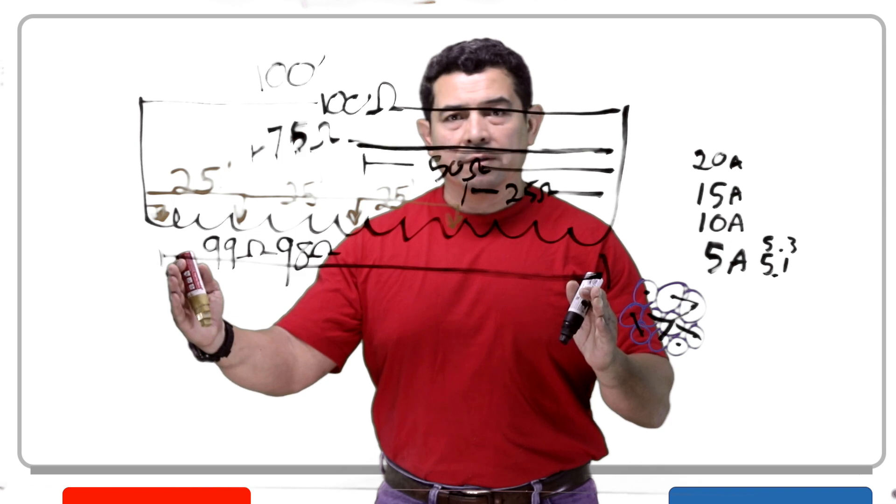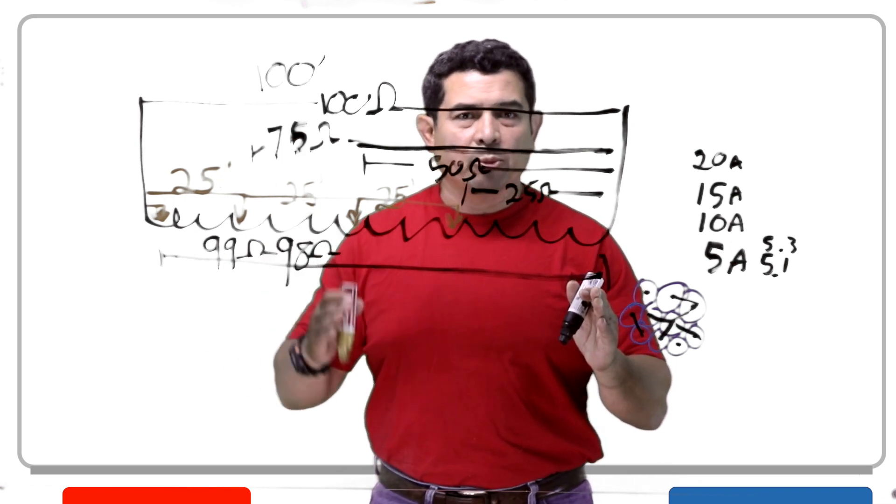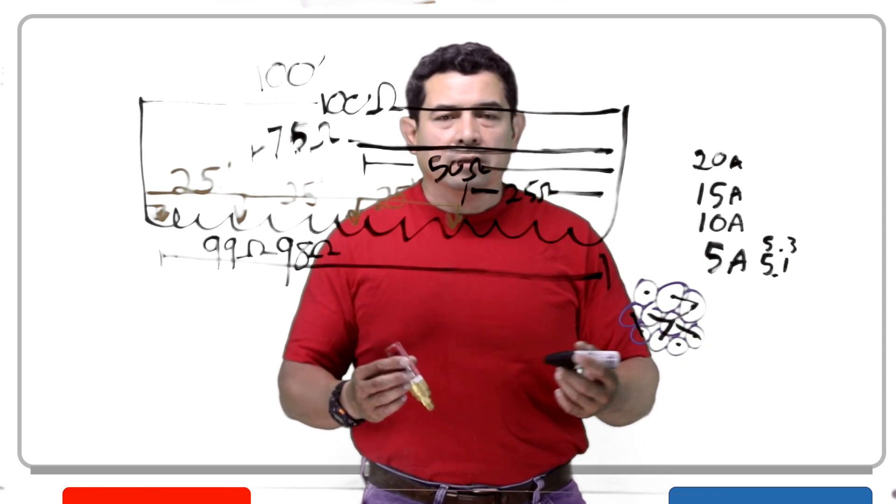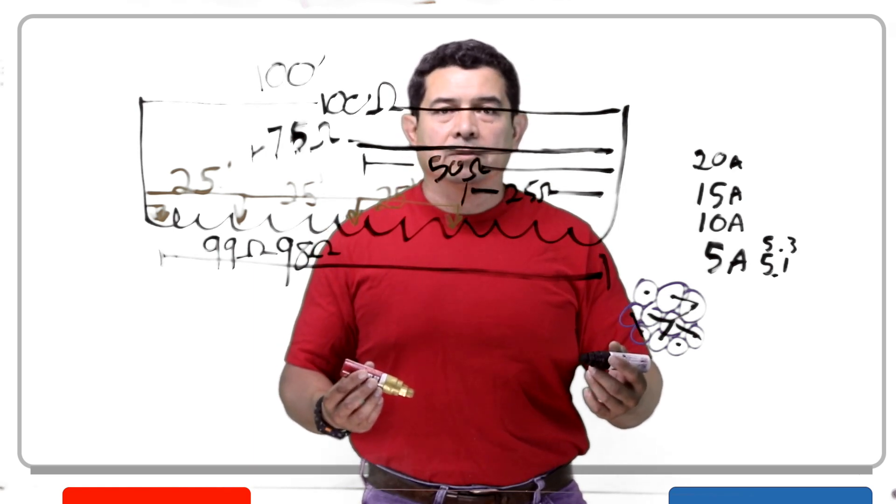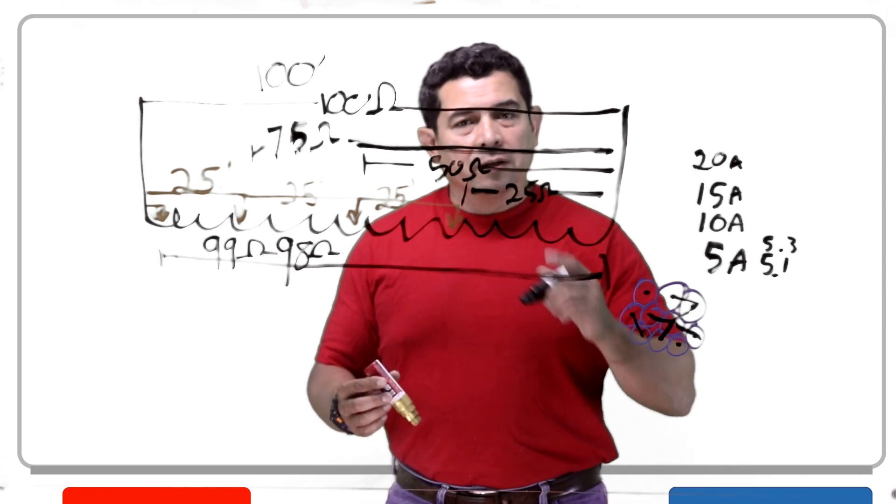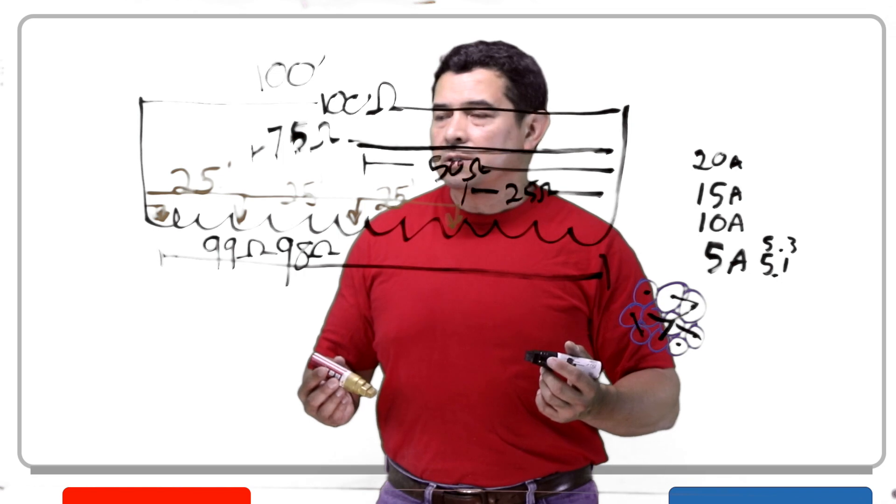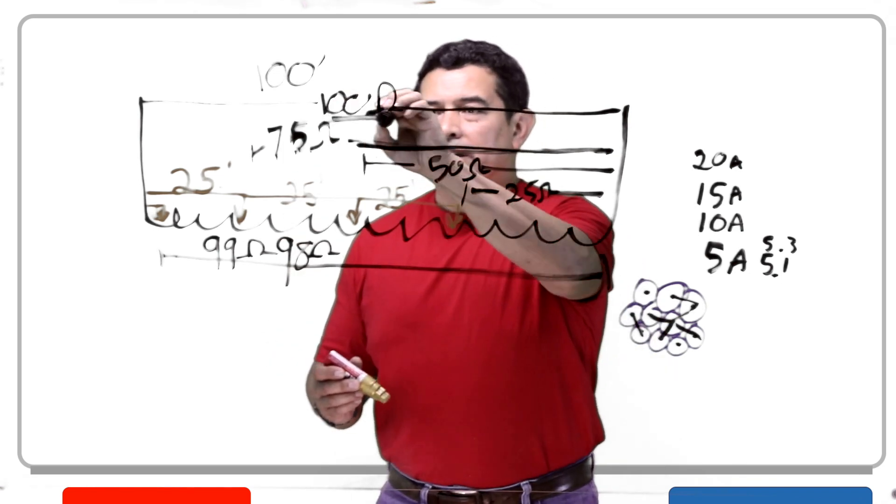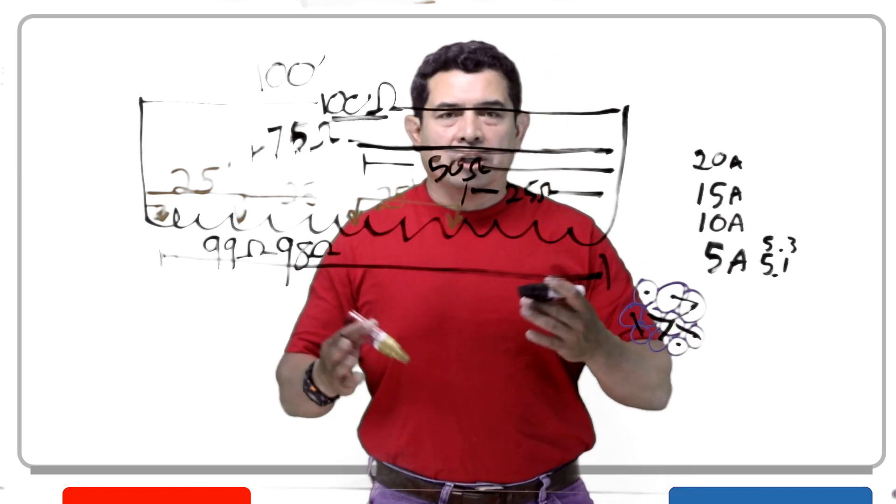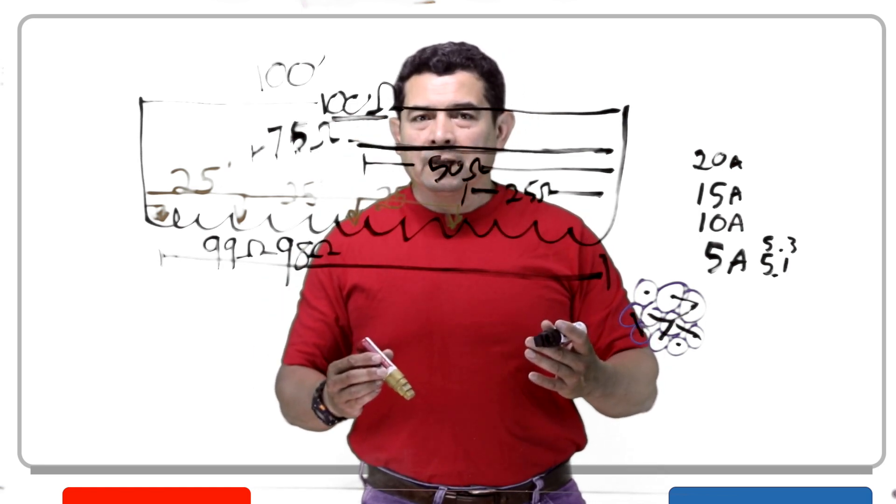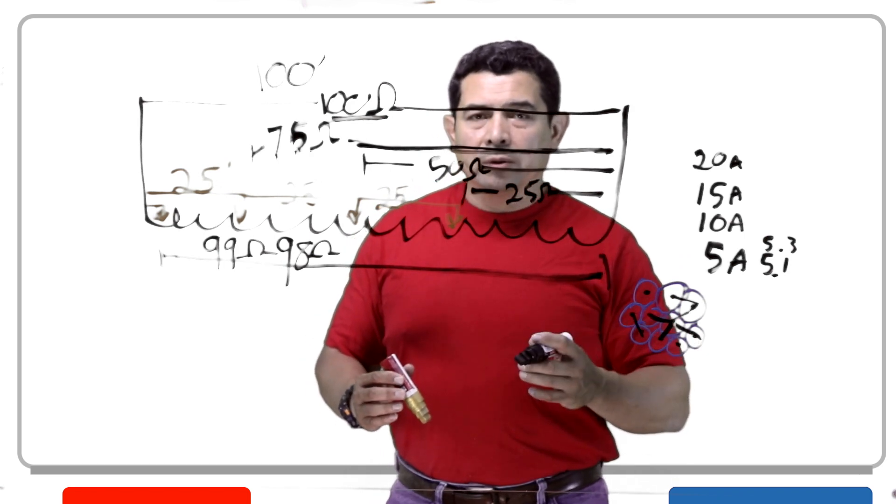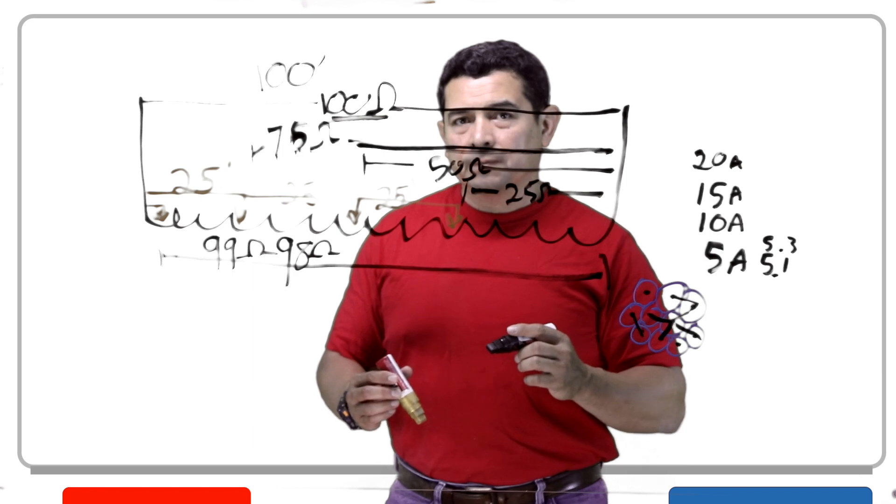Now, when we have a very slight short, it's not going to affect us that much, but we still have a problem. Let's say that you have a motor that you just paid $600 for. Do you want this motor to fail on you prematurely? No, you don't. We definitely don't want to do that. One of the things that we could do is to check the amperage. When we first install it, you check the amperage to see what the amperage is. The other thing that I always suggest is to check the resistance. See what the manufacturer says that the resistance should be. Now, this is a brand new motor, so you should have the correct resistance. Depending on the size of the motor, you can come back a year later. Check the resistance. If the resistance is still the same, then you know your motor is doing well. If your resistance starts to drop and drop and drop, then you know you're having problems with the motor, and you may need to order another motor and have it handy so that when this motor fails, you can go ahead and replace it.